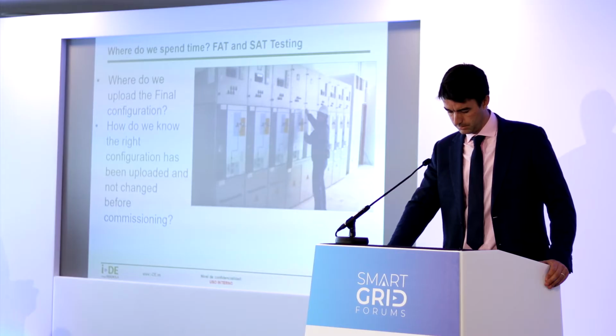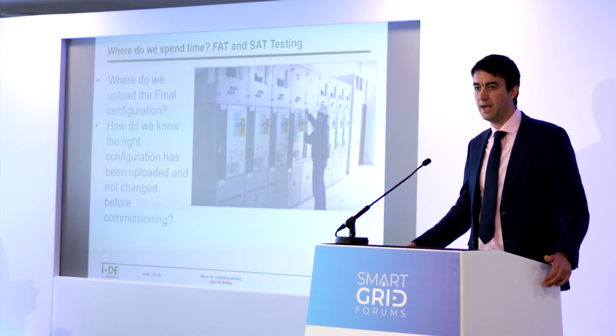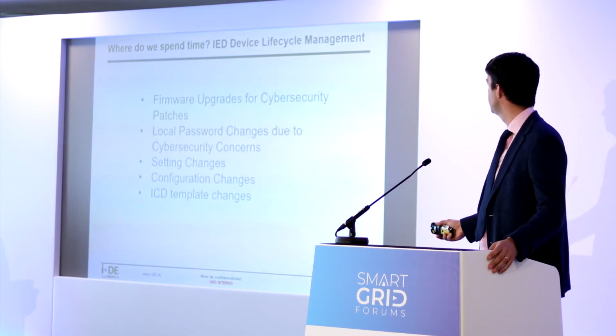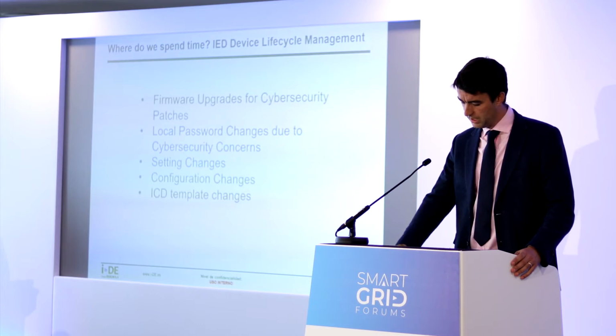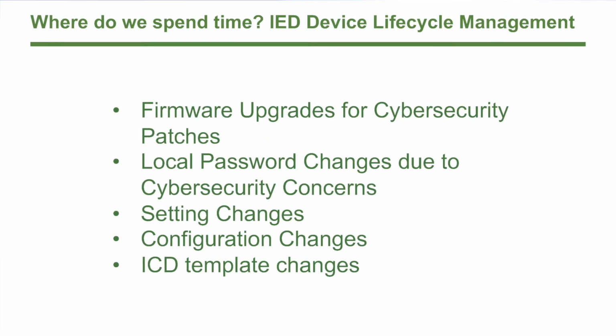So therefore, separate point-to-point tests need to be carried out for commissioning for the SCADA system, especially because our substation HMI previously used different templates and a different information source from the substation gateway.